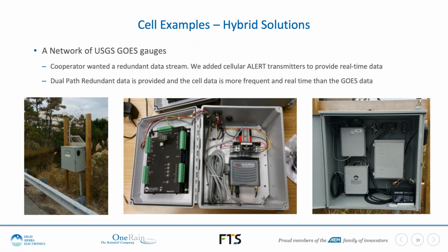Basically, we're in something called a listen-only mode, where the GOES DCP is reading the bubbler here, and as any reading comes across, they're doing 5-minute readings now to get that more frequent data. We're listening in on that, picking it up and transmitting, so they're getting 5-minute data. So just an example of how you might blend telemetry solutions.